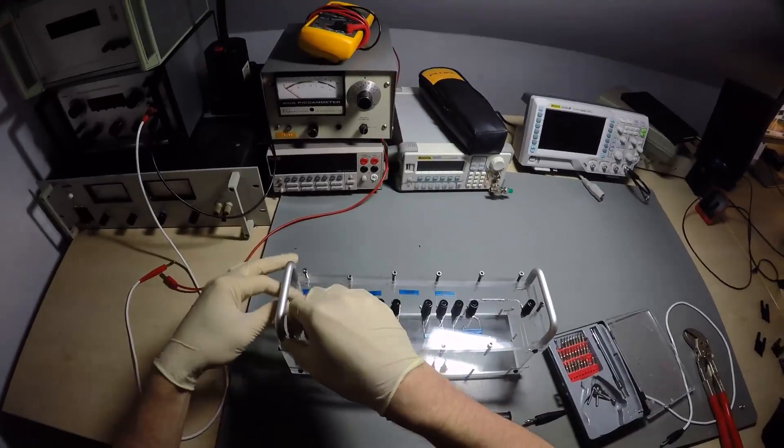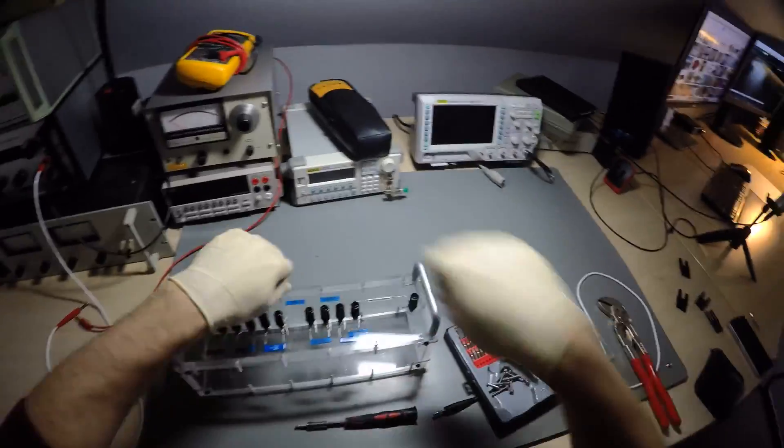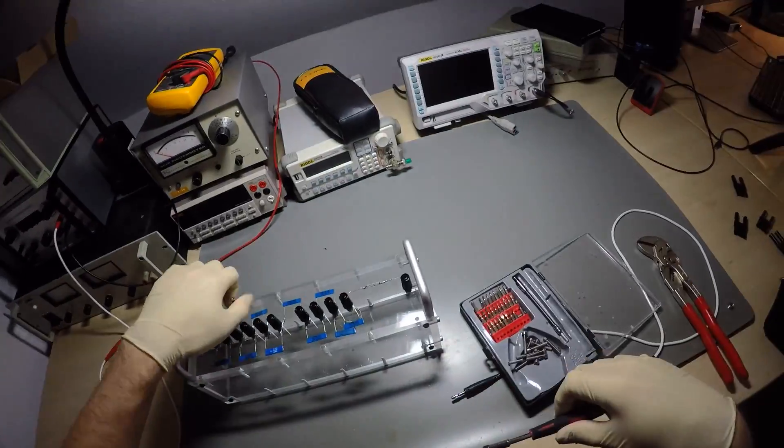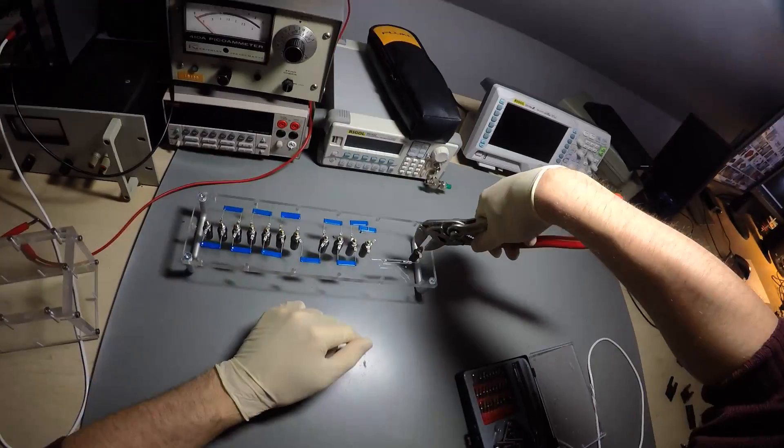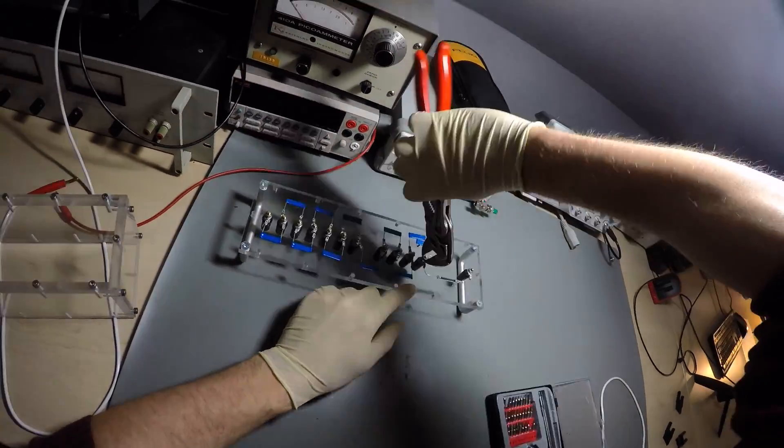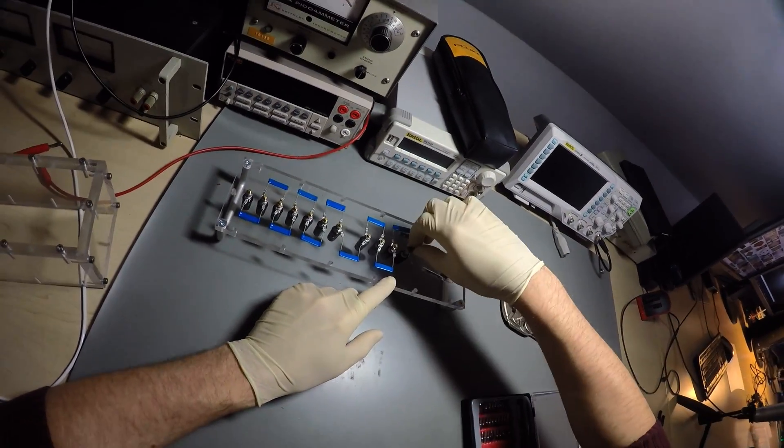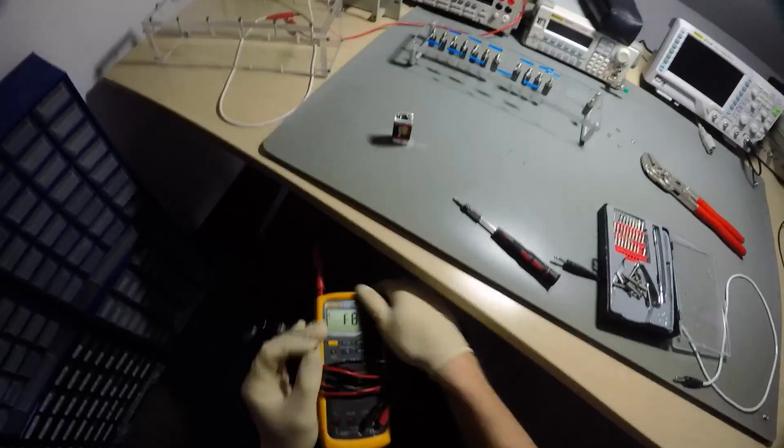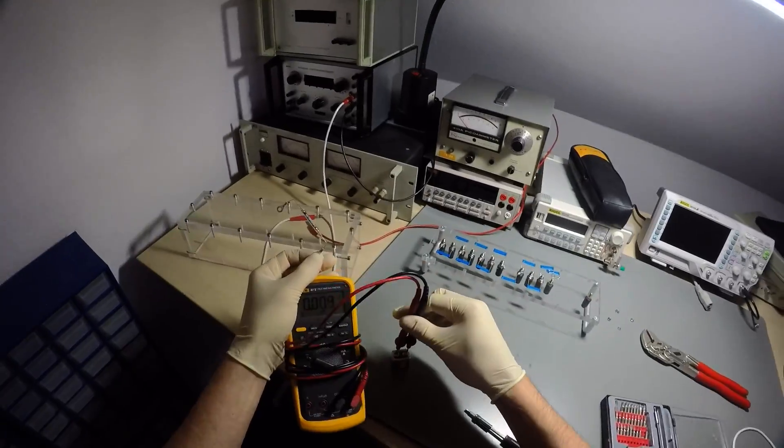I have a feeling that this video is getting a little bit long, so I'm just mentioning this one for completeness sake. Whenever really high sensitivity is required, it is a good idea to use a shielded can with tri-axial cable inlets for your experiment. Neither do I have tri-axial cables nor does the Keithley 410A have a tri-axial input, but I happen to have an old aluminum enclosure with a BNC inlet. And that should be suitable for keeping most disturbances out I think.